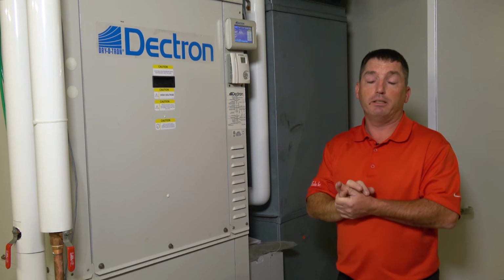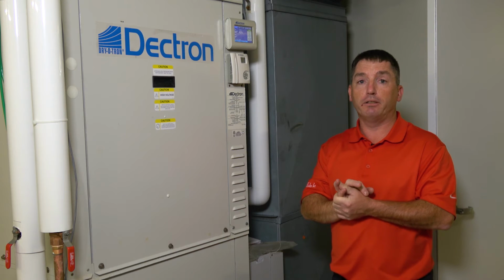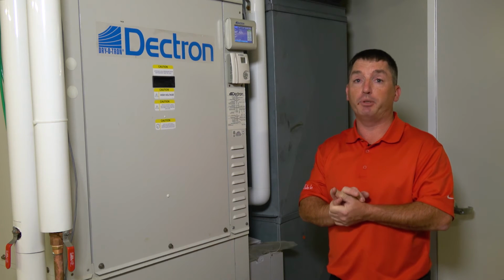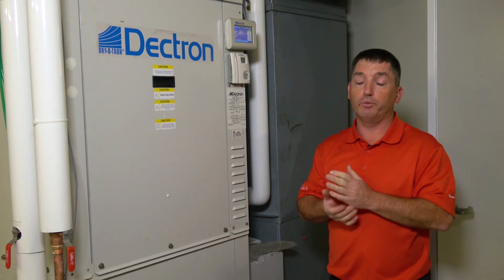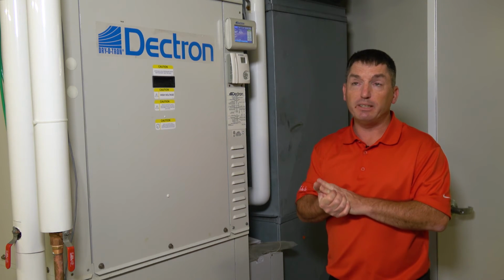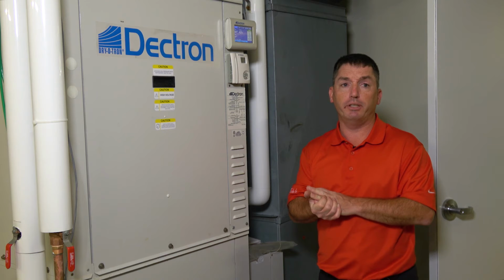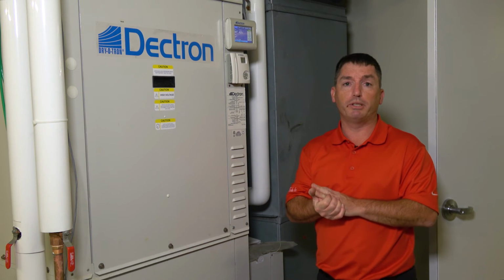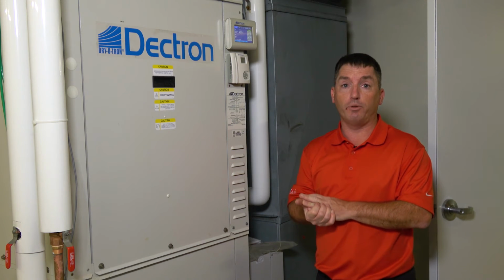Normal design is we try to maintain our relative humidity at 50% or lower during unoccupied periods, and room temperature typically in the area of 85 degrees, which means the pool would be somewhere in the 83 to 84 degree range.